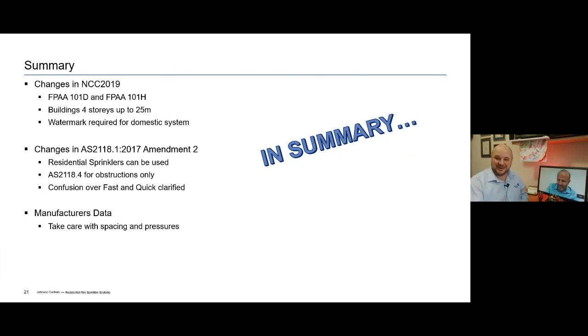For residential, this is a great one actually. For a residential building with a car park with more than 40 cars, so I'm going to have an AS2118.1 system there in the car park. Can I use AS2118.1 for the car park and then use a FPAA 101D system for the residential part? Yes, you can. There's nothing in the NCC that prevents you from doing that. Okay, so in that case you're going to be saving on some valves and so on as well. And potentially routine service of flow switches and all the things that would potentially go up that building as well. Yep, sure. Up to 25 meters, so low rise only.